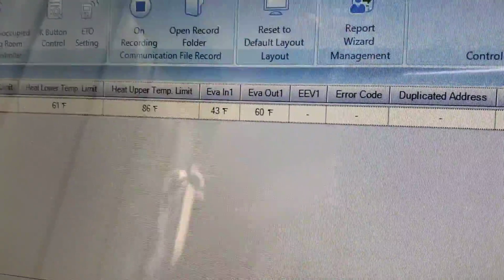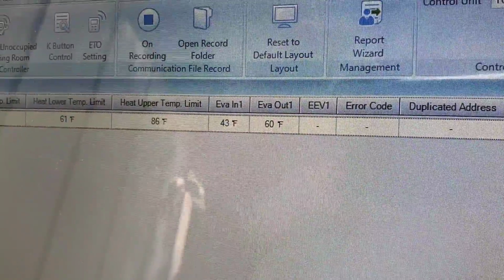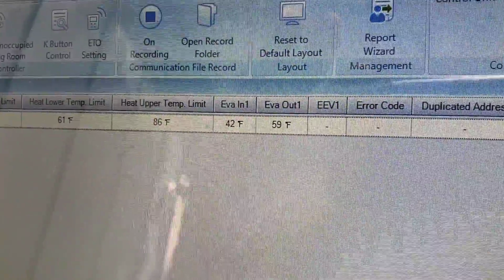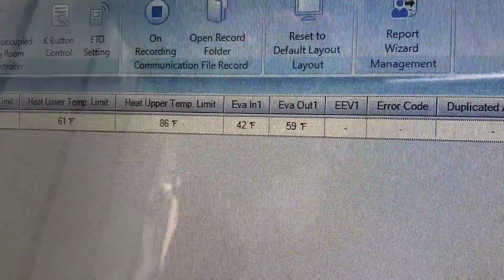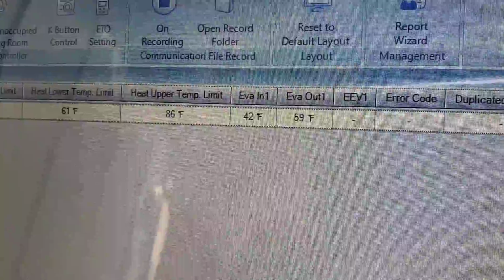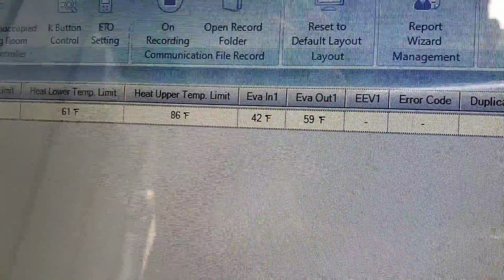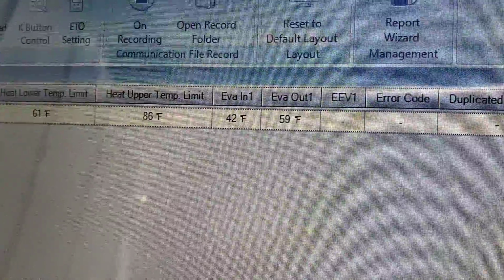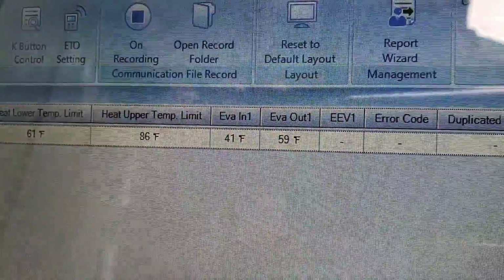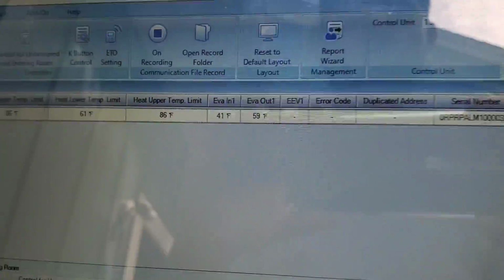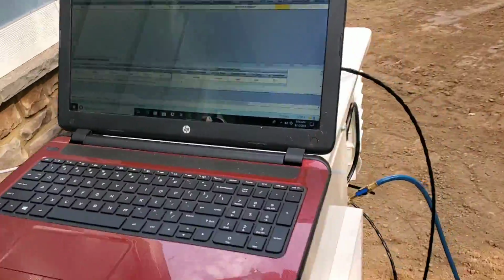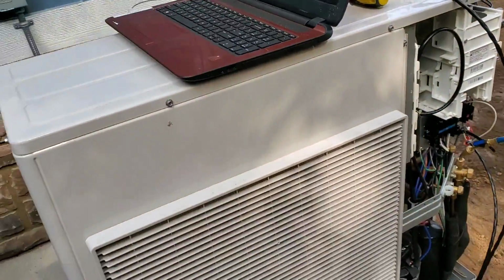I've got my gauges hooked up and I have added some refrigerant. Now the evaporator inlet and outlet are getting a lot closer. Evaporator inlet was 58, now it's 42. So it's 42 degrees on the evaporator inlet, which is great. Outlet is 59, so that's going to get a lot closer. Remember, if you go to charge one of these Samsung pieces of equipment, you need to factory charge it.